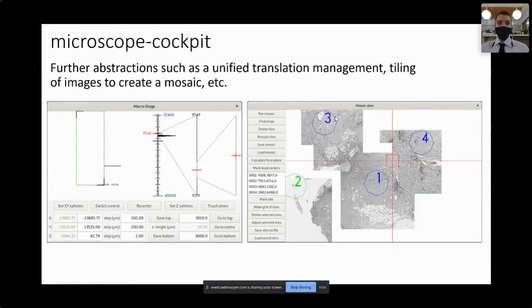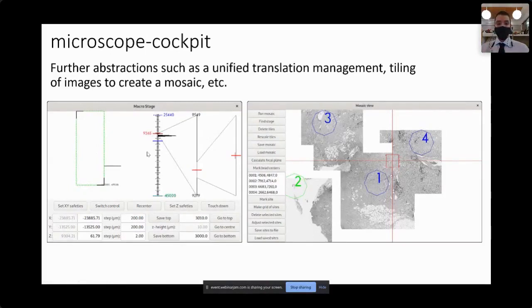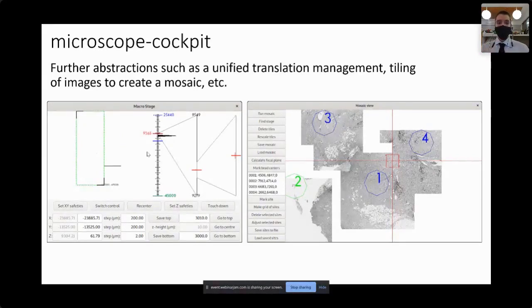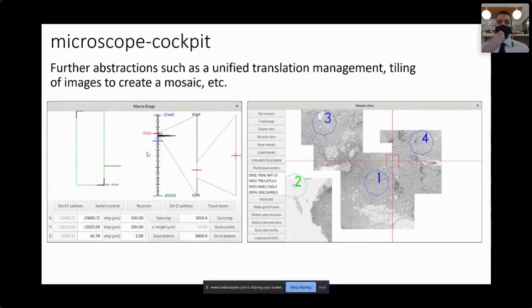The unified translation management introduces the concept of a macro stage. You can see an x and y stage together with a z stage, and Microscope Cockpit synchronizes control between them to let the user specify a precise location in x, y, and z space, and to specify steps or save specific locations to refer to during an experiment. The mosaic view allows you to perform experiments by sweeping in a spiral pattern to create a mosaic of your specimen, or to select specific regions of interest to revisit during an experiment.